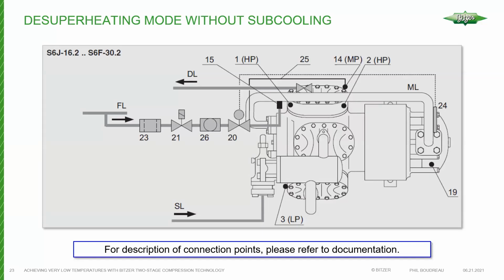I've seen systems where both methods are used, but to be clear, if you're going to ever apply desuperheating mode and subcooling mode, please consult with us on this so we can work together on that. You have to be very careful. And just to be very clear, you never, ever want to use these two modes at the same time. Okay, it's one or the other, never both. Preferably pick one and go with it. But I've seen some sophisticated systems where, for whatever reason, the additional desuperheating mode was applied. For example, for capacity control was one way of doing it.